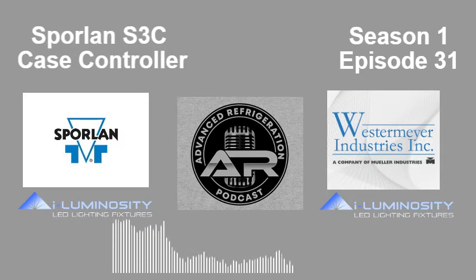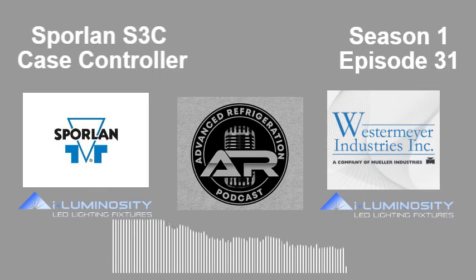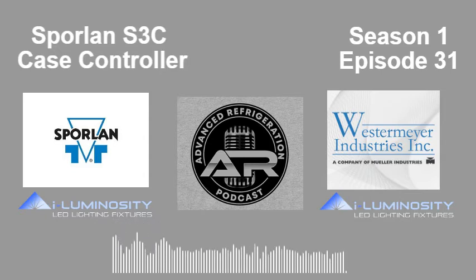Yeah, I see that a lot on startups. I see cases that'll randomly run too cold because obviously we have glided refrigerants, and at times you get a little lower discharge air out of it. We get some nuisance alarms out of it. I didn't know if it was able to float that set point or not, but it makes sense. There's been a couple cases with discharge air control.